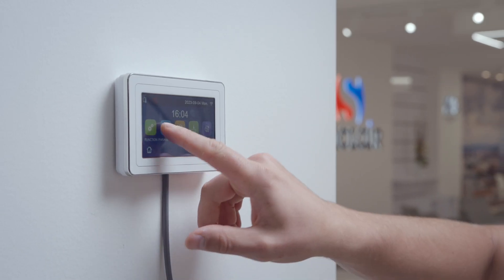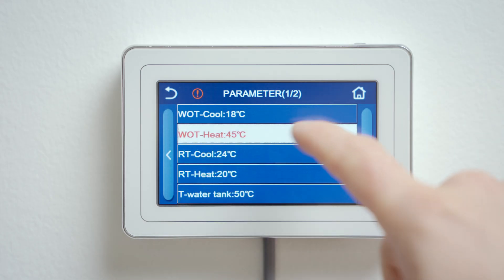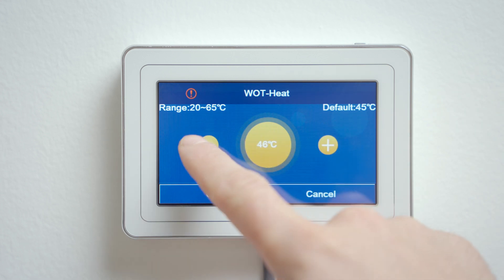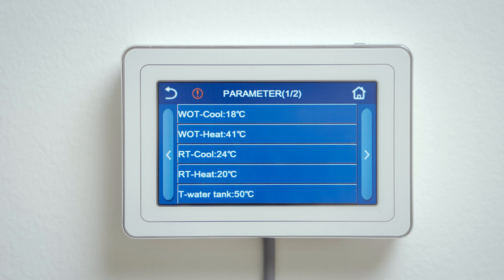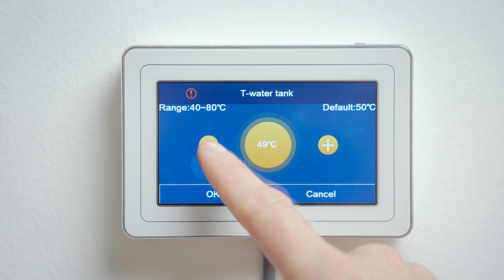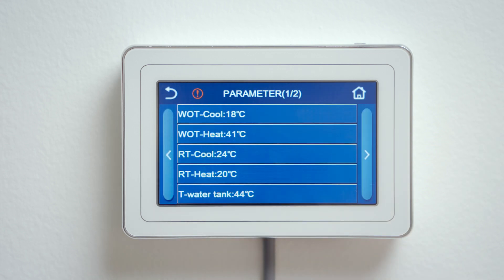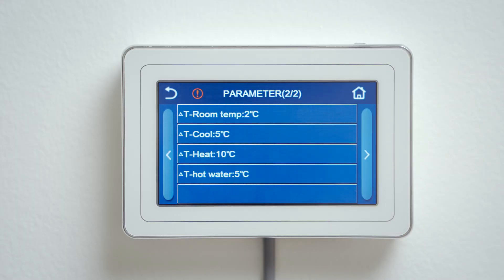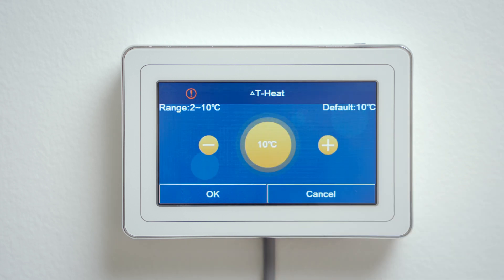All that remains is to set the desired temperatures. Return to the main menu and select parameters. On the second line, WOT Heat — here select the desired temperature at the outlet of the heat pump; this is the temperature that will enter the heating system. On the fifth line, T water tank — here select the desired temperature in the domestic hot water tank. On the next page, hysteresis can be set. On the third line, the drop from the target temperature is set, after which the heat pump starts heating again.